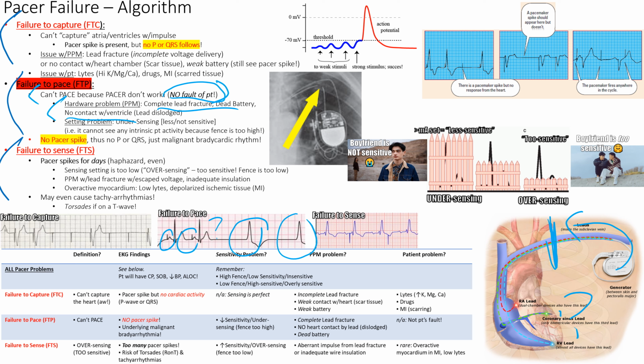Another reason could be that the lead has just traveled out. It could be sending little impulses, right? But it's not in contact with the ventricle. Therefore, it's going to be a failure to what? Failure to pace. Okay? It could be a setting problem as well, where the settings are not correct. The settings meaning we're looking at sensitivity, because remember that first slide was really confusing, right? All that was revolving around sensing. And right here, we're usually sensing the ventricles. That's the most common pacemaker we look at.